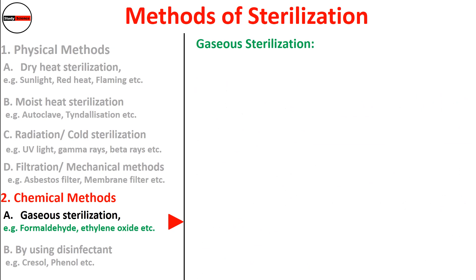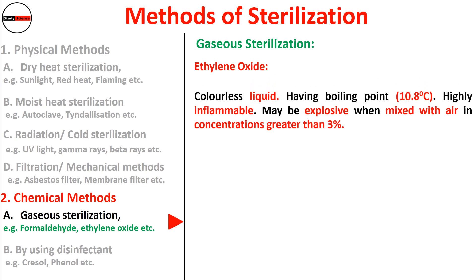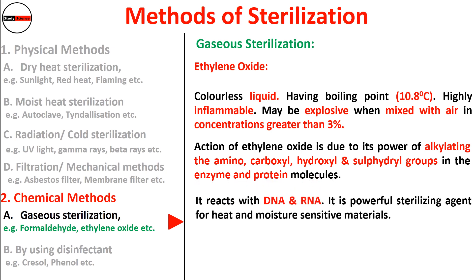Ethylene oxide is a colorless liquid with a boiling point of 10.8°C, making it highly inflammable and potentially explosive when mixed with air at concentrations greater than 3%. Its action is due to its power of alkylating the amino, carboxyl, hydroxyl, and sulfhydryl groups in enzyme and protein molecules. It reacts with DNA and RNA, making it a powerful sterilizing agent for heat- and moisture-sensitive materials, used for biological and medical preparations.